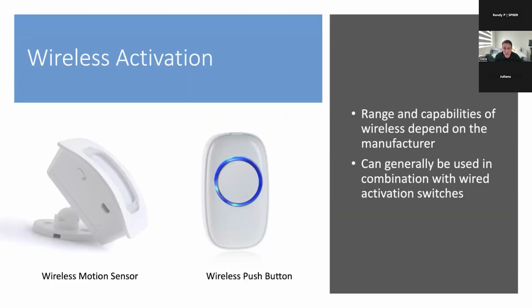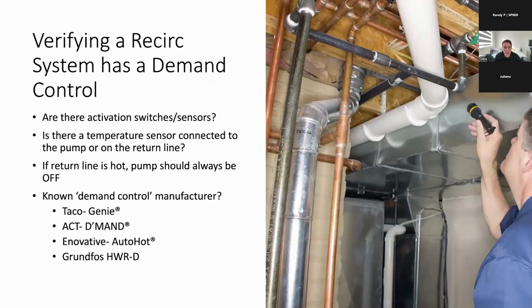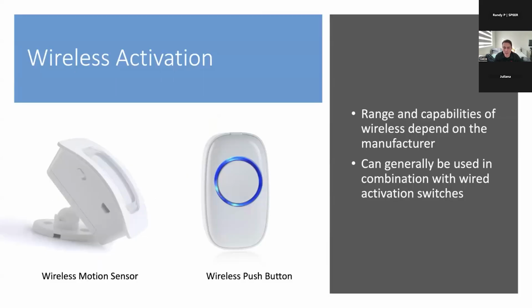There's wireless activation, so you can operate the system from, and this is great for retrofit because you don't have to run low voltage wiring. So typically these have a range of about 1,000 feet in open air, so you can literally keep one of these buttons on your nightstand. So when you wake up in the morning, hit your alarm clock, hit the little wireless button, and the time it takes you to walk to your bathroom, the hot water's already there and the pump's already turned itself off.